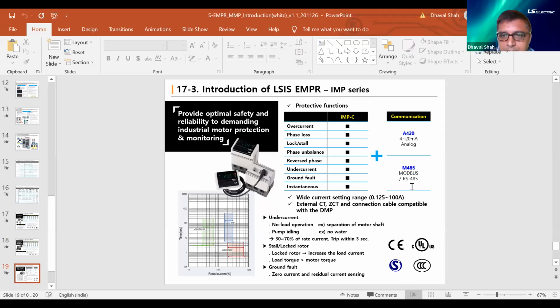IMP is available with RS 485 and 4 to 20 milliamps, has an inbuilt protection, and can be available from 0.125 to 100 ampere. So this is the product range. Like a few of the settings which Rajesh already mentioned, 30 to 70% of the rated ampere can be set and trip within 3 seconds.